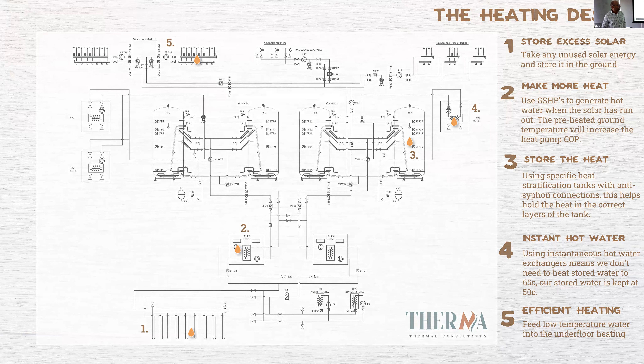And then the last one was efficient heating. So running in-slab heating, we only had to run it at about 40 degrees going into the slab. So for all of this system, those tanks, 50 degrees was the hottest we ever needed to get the system. Any other system, you'd probably have to run that up around 65. So that was a big saving for us.